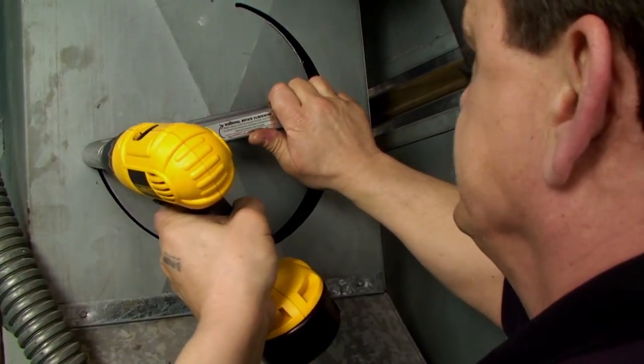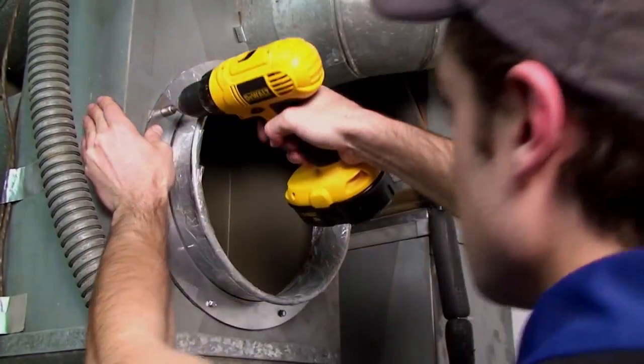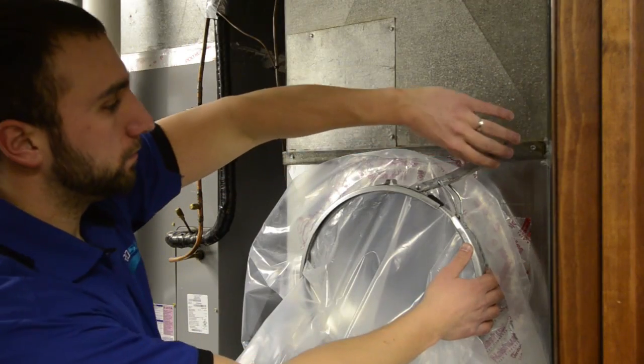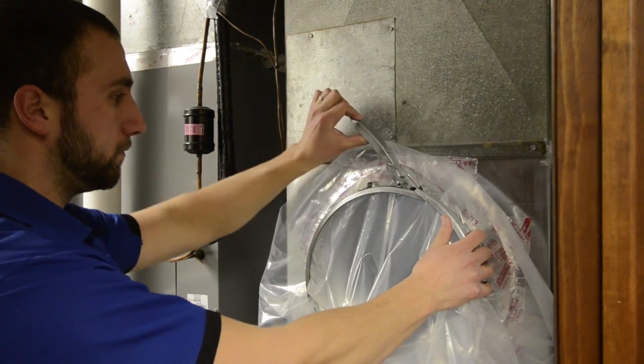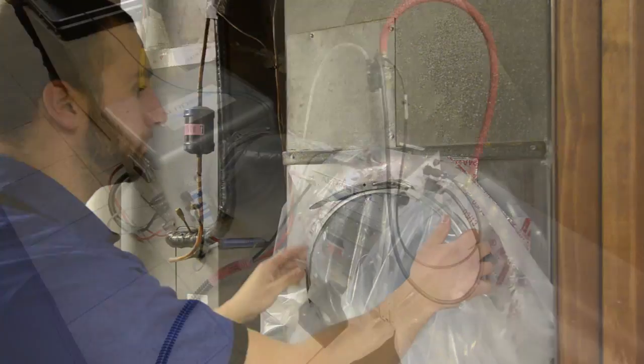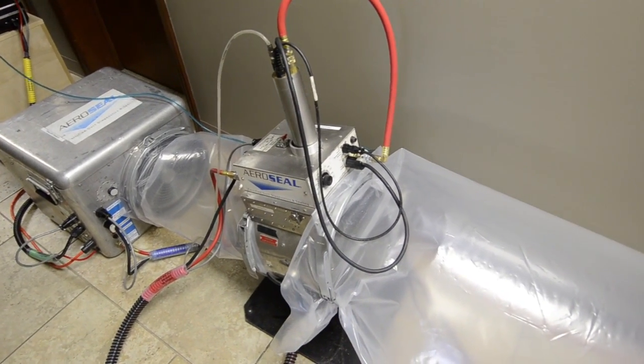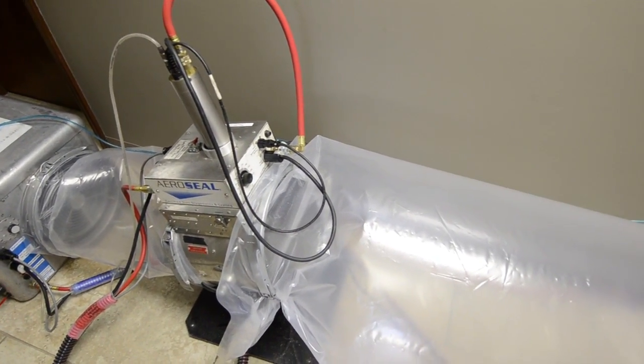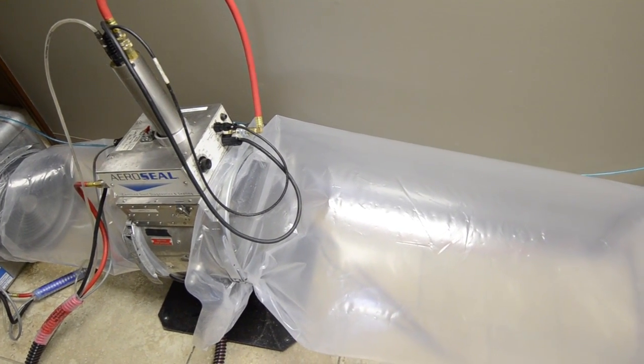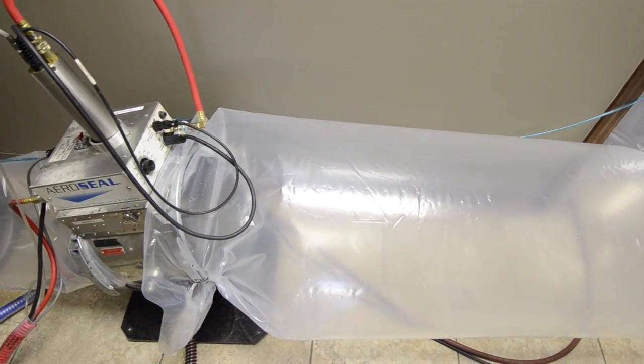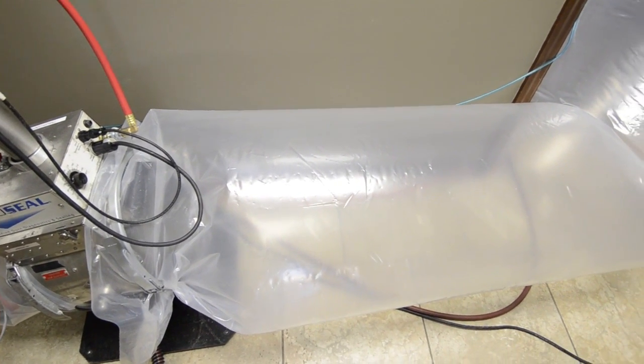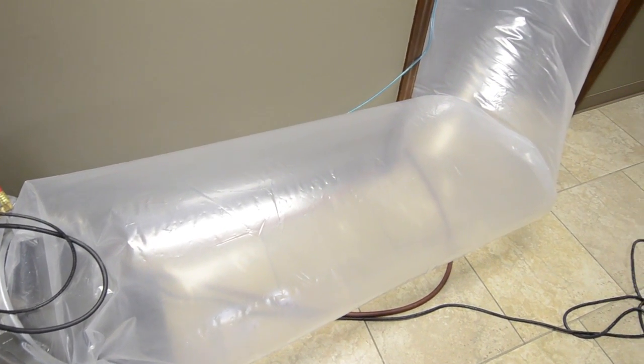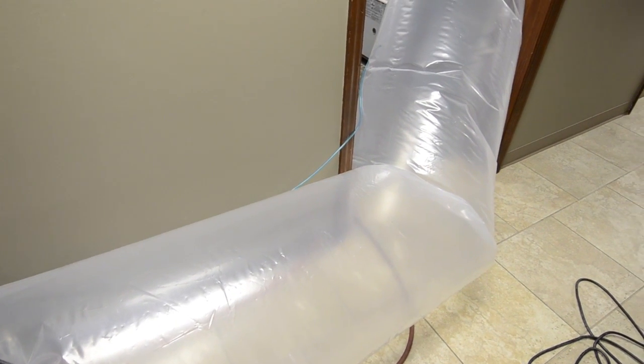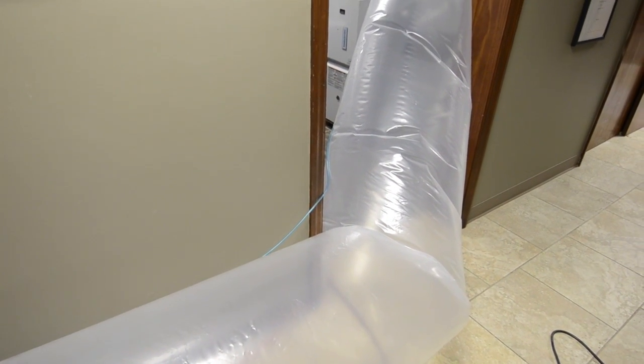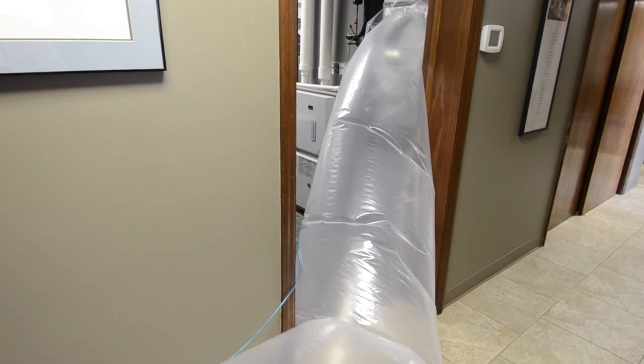It is now time for the Aeroseal job to begin. An access hole is cut into the supply or return plenum, and a temporary collar is attached. The Aeroseal injection machine is connected to the duct system using a long, flexible plastic tube. You should know that there will be multiple injection points in most commercial Aeroseal jobs. At least one per vertical riser and at least one per each main horizontal trunk. It is also important to mention that some jobs can be completed in one day, while others may take several days, depending on the size of the building and number of injection points.